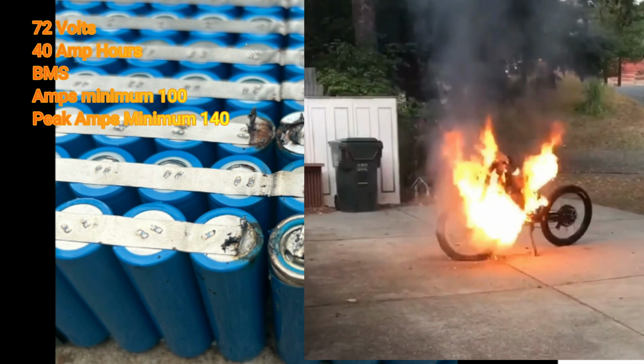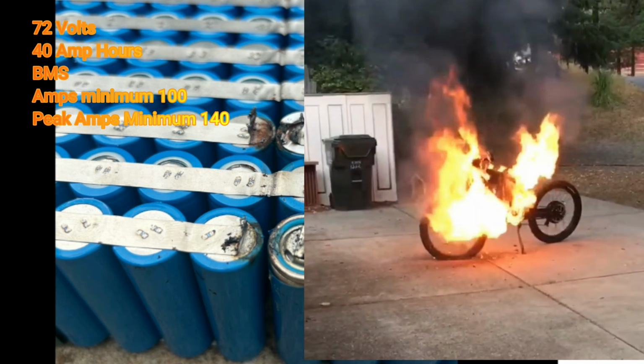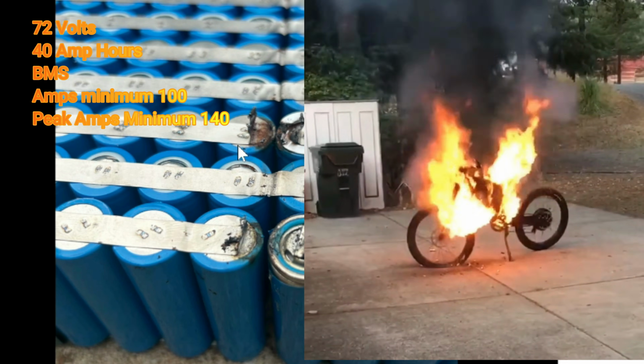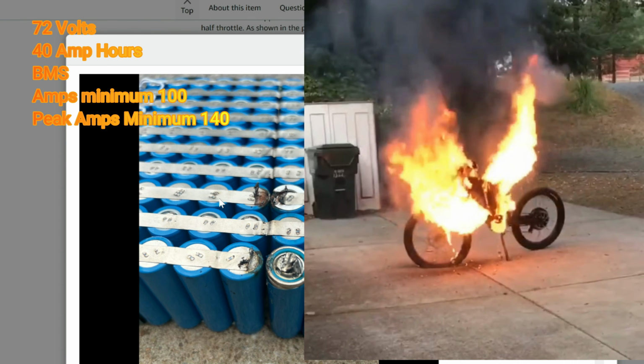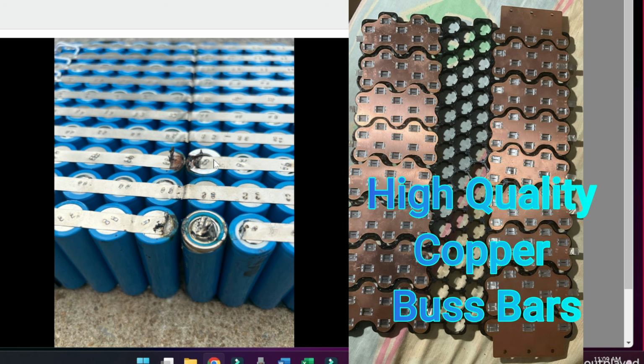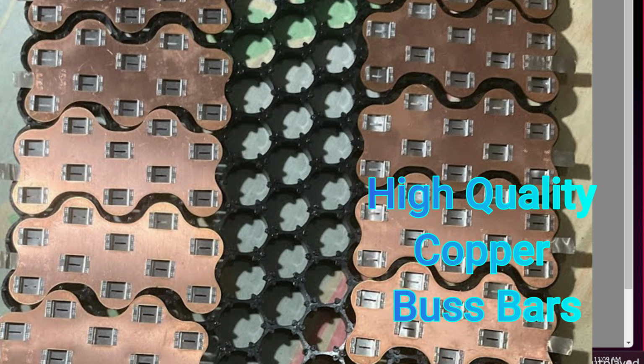The battery manufacturer limits this with the BMS so you can't overdraw on the amps. This manufacturer did give it a BMS rated to pull 200 amps. The problem is this battery isn't built high enough quality. Look at these tiny thin strips. Because of that low quality, they overheated and caught fire when he pulled 200 amps.